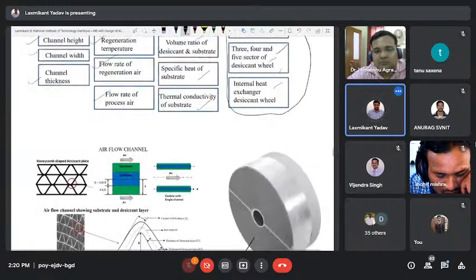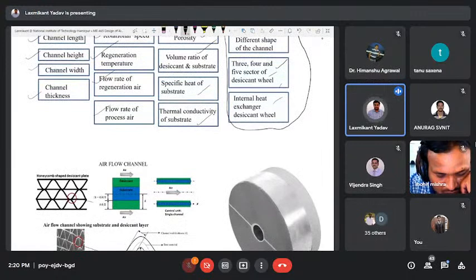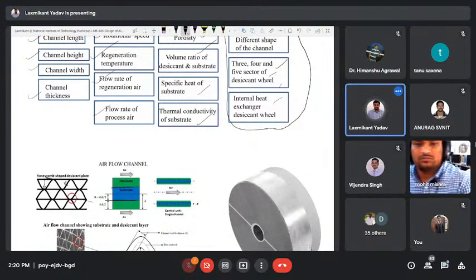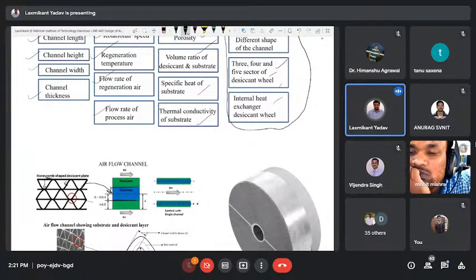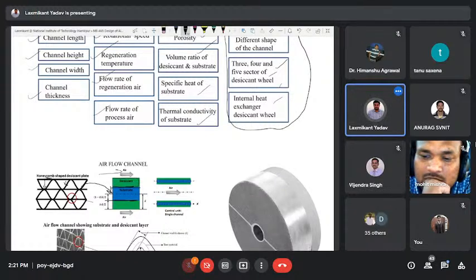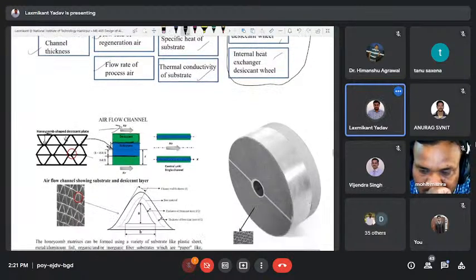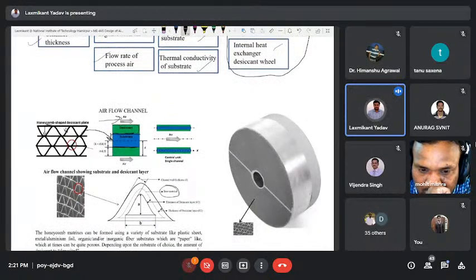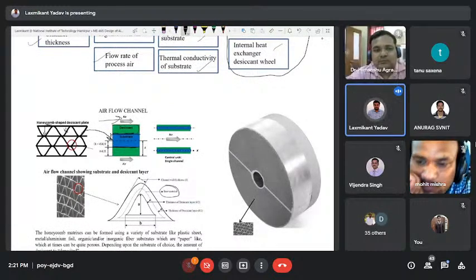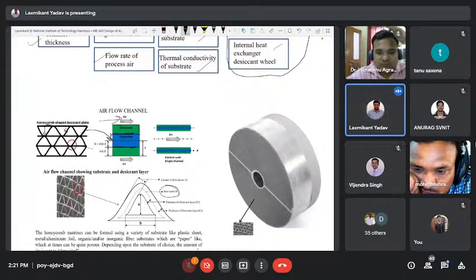Okay. So you can see this is the channel of the desiccant. This is the height of the channel and this is the pitch of the channel. So these are the design parameters, and this is the thickness of the channel where air flows, and this is the substrate. This is called the substrate. So this thickness is represented here. The substrate material is made of fiber. On that fiber we coat the desiccant layer. So when air flows here, moisture transfer takes place from air to desiccant due to the vapor pressure difference. Okay, so here we can see this base material is called the substrate, made of fiber, and this is the thickness of the desiccant coating on this side. So these are the design parameters.